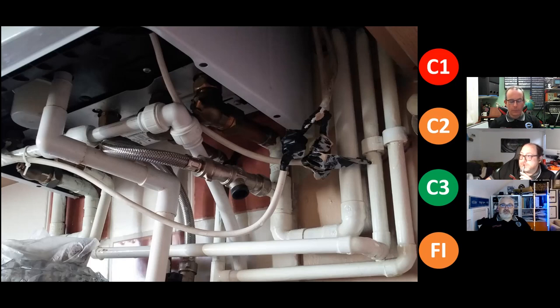It's a minor works, it's under 7671 scope. That's from the head of the wiring regs committee themselves. We definitely need to do a webinar, probably next year, because we'll be busy, that covers and explores this a bit more. But for me, that's a C2, just based on the fact them terminations are rubbish, and that could be accessed by an unskilled person or a child. It's too much of a risk.